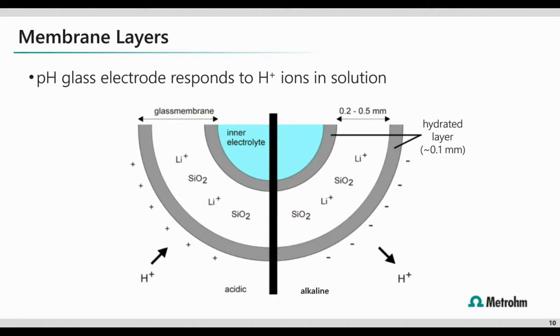So the image you see on your screen now is a cross-section of the membrane bulb. So again, this is the ion-sensitive part of the electrode. The membrane is constructed of special glass, and this is the area in the image where you see the silicate skeleton that contains kind of the lithium ions and among other things floating around in there, okay? On either side of that glass, there are 2 very thin gel-like hydration layers. So in your image, those are the gray kind of half moon shapes. So thinking about the outer hydration layer, this is what actually comes into contact with our sample solution, while the inner layer comes into contact with the electrolyte solution.